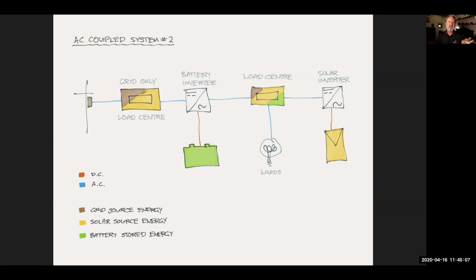If you look at this diagram, you'll notice there's a battery inverter which has two AC ports, a grid port and a load port, so it has two AC feeds going into that one inverter. What's different about this battery inverter is it will accept power on its load port, the right-hand side of this diagram, and it's capable of charging its battery from that solar inverter system independently of the grid.